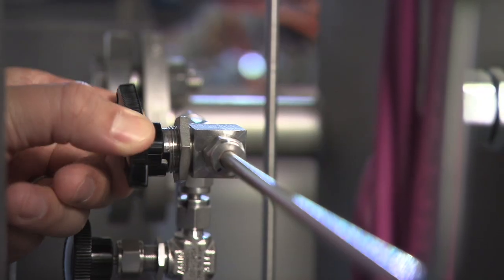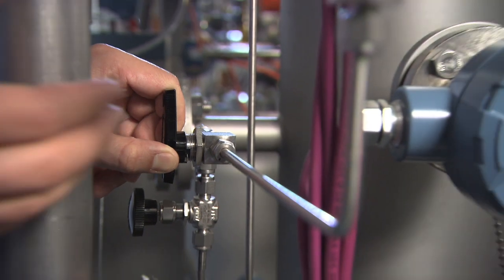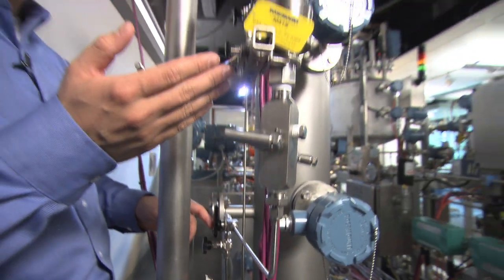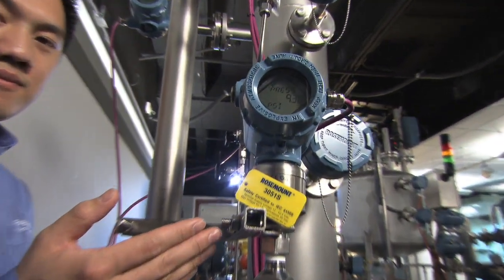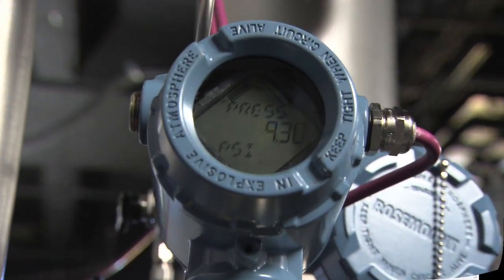And until now, this kind of dangerous failure condition has been difficult to detect and could prevent your safety system from responding to unsafe process conditions. So to demonstrate this type of failure, I'm going to slowly close this valve on the impulse line that's leading directly to the 3051S pressure transmitter.